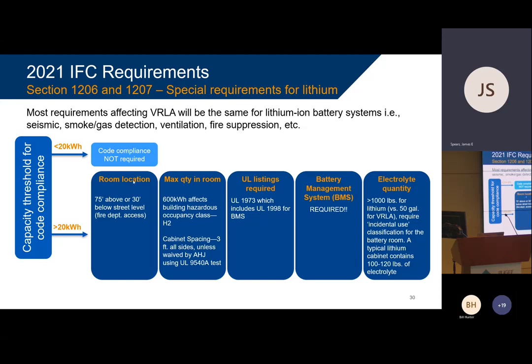So the new code says the room location for this lithium battery shall not be more than 75 feet above or 30 feet below the lowest fire department street level, typically street level fire department access. That's to make sure that the ladders on those fire trucks can reach that room. And that's a requirement. You have to get a waiver from the authority having jurisdiction if you want to put that battery on the 29th floor, regardless of how small and light it may be.